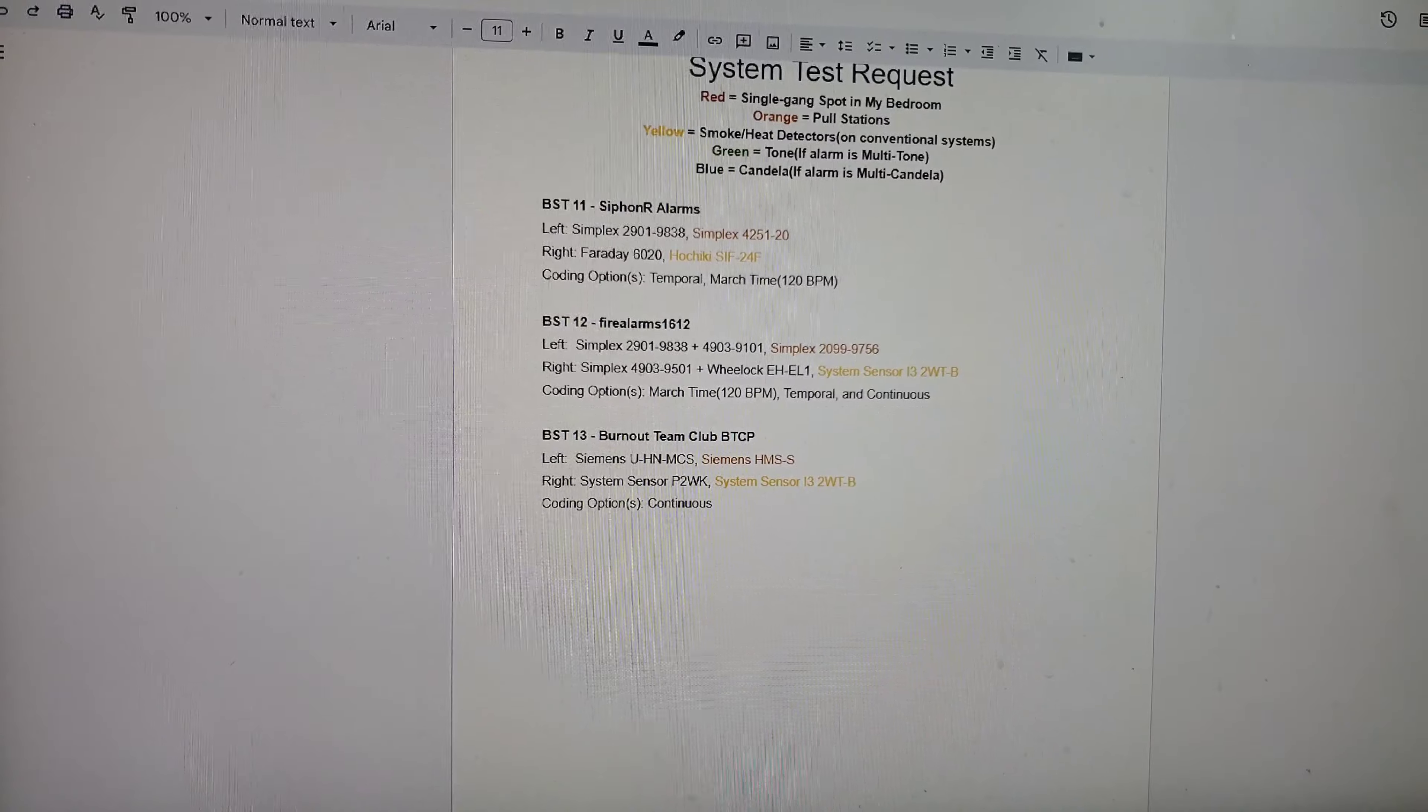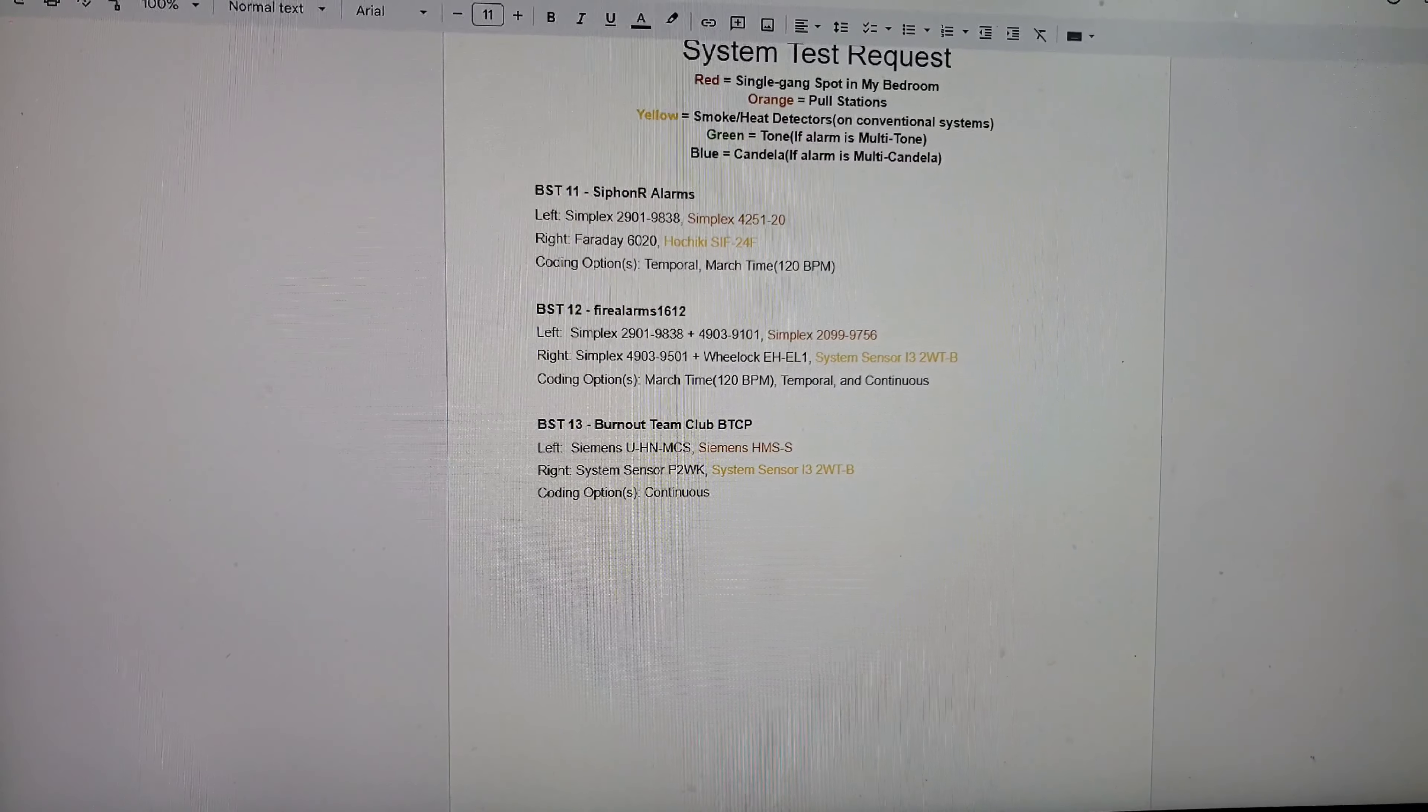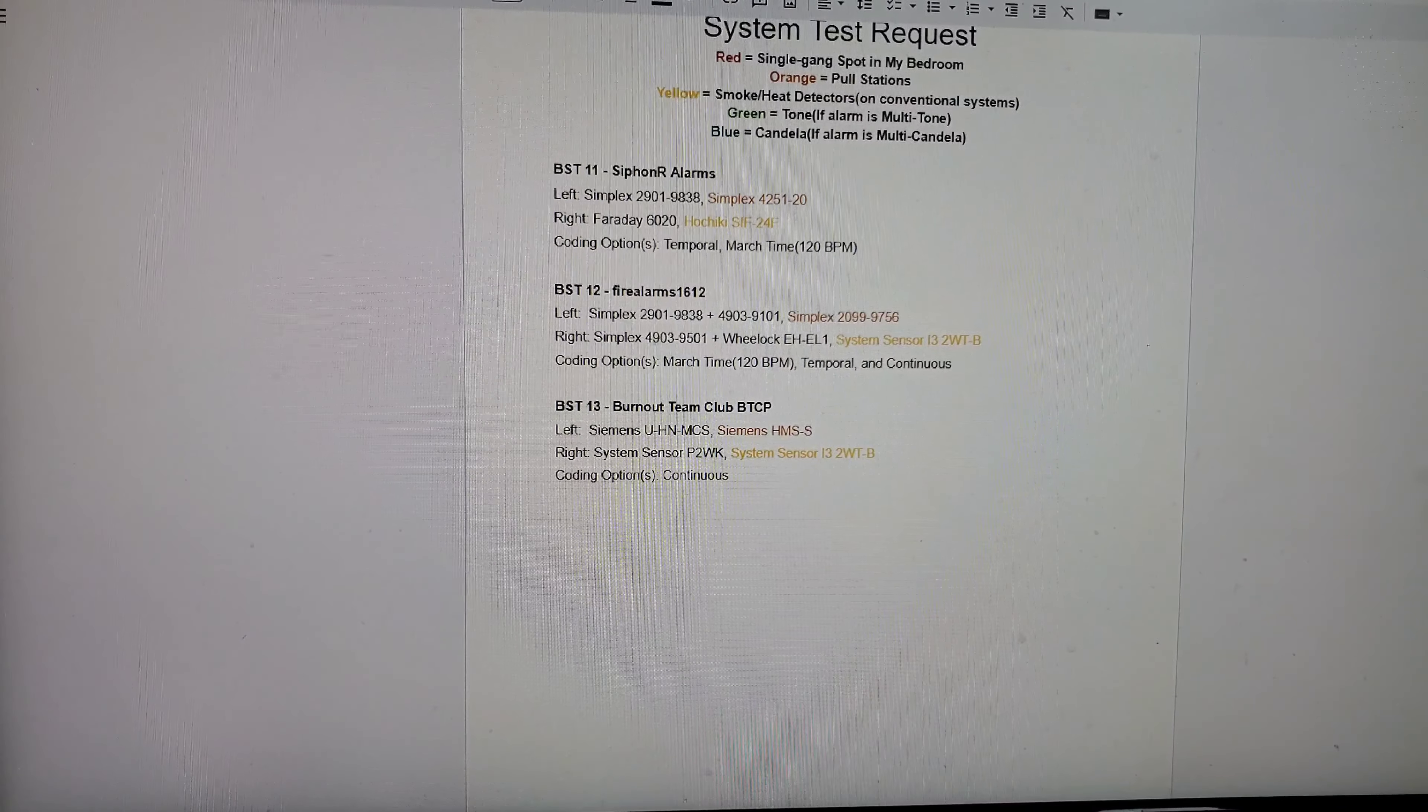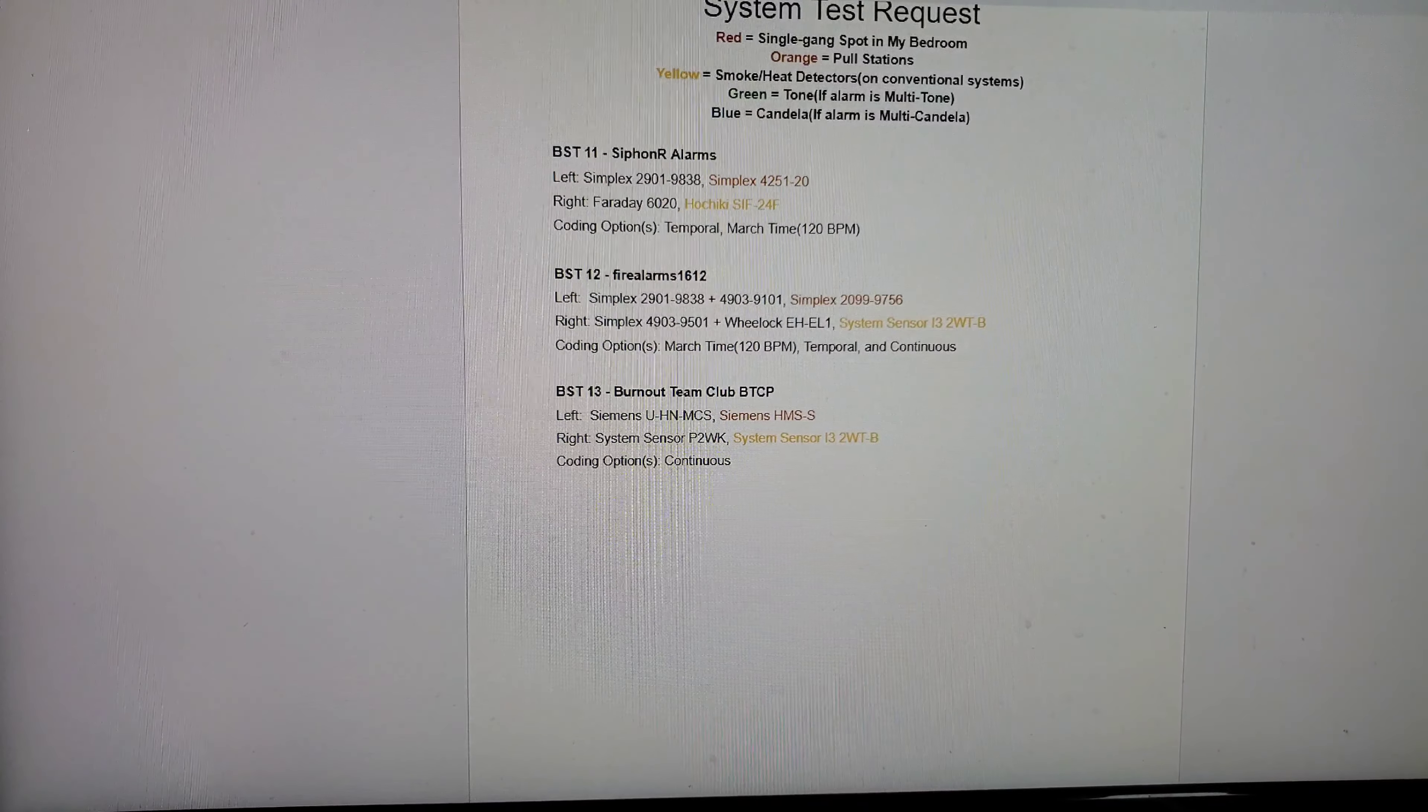So this request is requested by Siree for alarms. This is on the MS-5UD. On the left side he requested a Simplex 2901-9838. And below for the pull station is a Simplex 4251-20. On the right is a Faraday 6020. And the smoke detector is a Hochiki SIF-24F. Coding options will be Temporal and March time 120 BPM.